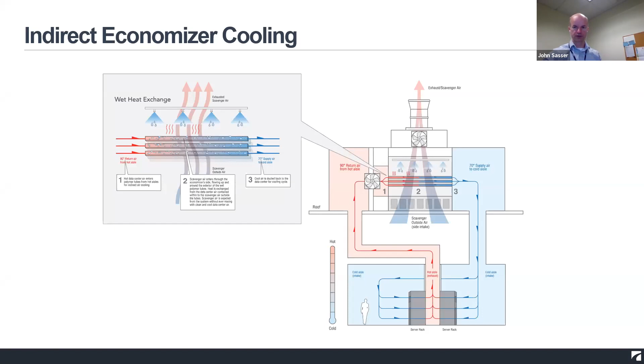It essentially has three modes. One where it's running dry and you're just rejecting heat through the heat exchanger. Then as the outside temperature warms up, you start to add water and cool down the temperatures—that works best in dry climates like we have in Central Washington. And in the hottest summer afternoons of the year, we turn on trim DX cooling to get the supply air temperature we're seeking.